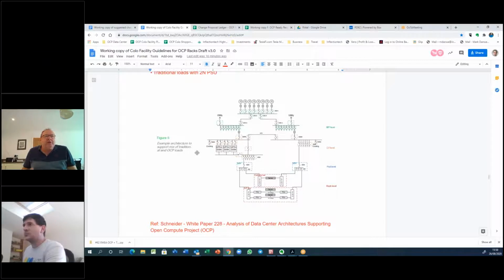Question for a decision. I'm sorry. Just real quick, a question for Brevin. Actually, I can see potentially more value going to the North American market with our crazy different voltages and stuff. For the OCP racks that you have with non-BBUs, are you feeding that 480/277, or is it 208 three-phase? And is there opportunity to educate there on how you feed 480/277 to power shelves?